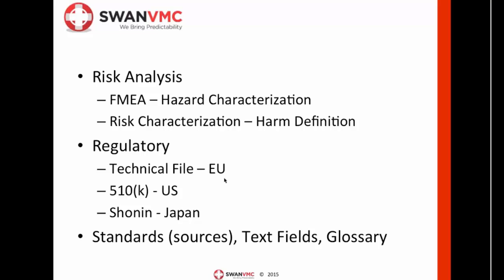That way, the risk analysis people don't have to pull in variables called local effects or system effects and try to figure out what that means to users. What you're just saying is, do the risk analysis with an FMEA and provide all the hazardous situations that could occur in the product or in the processes.